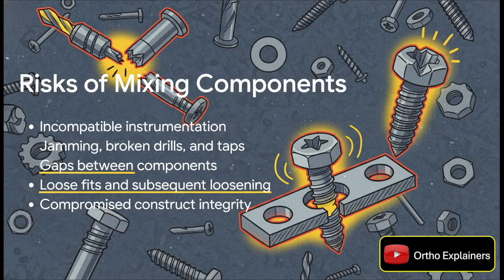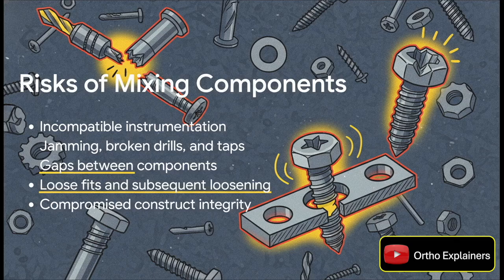The risks here aren't just theoretical or metallurgical — they are immediate and mechanical. You can run into incompatible instrumentation right there in the OR, leading to jamming, broken drill bits, or stripped screw heads. You can create microscopic gaps between plates and screws from different systems, leading to a loose fit, toggling, and eventual loosening of the entire construct. The bottom line: the integrity of your construct is compromised from the moment you mix components.